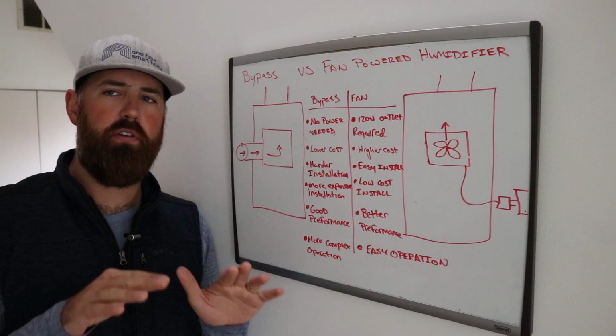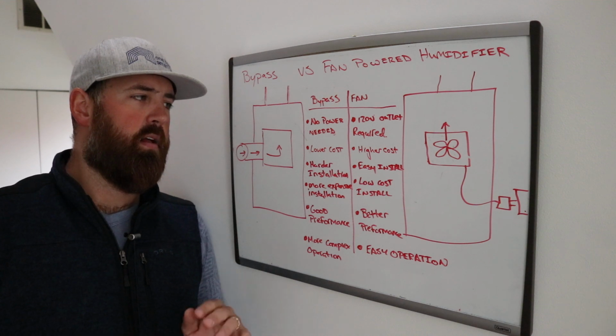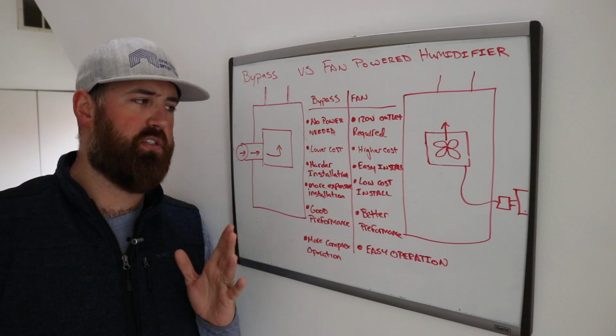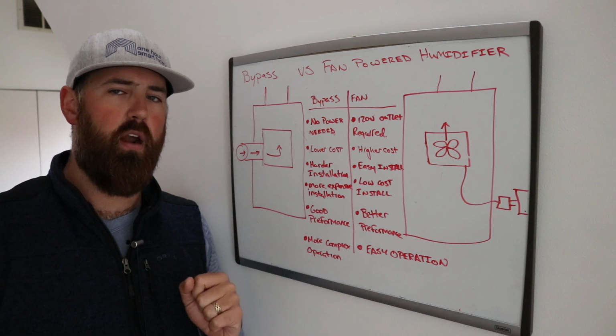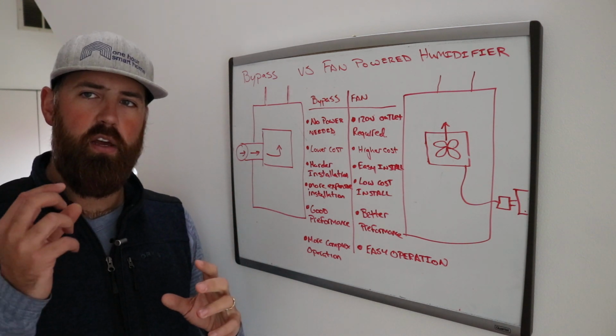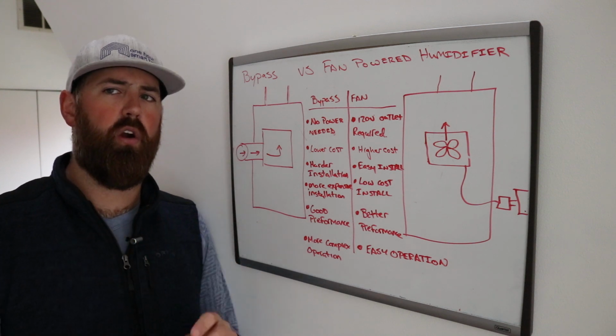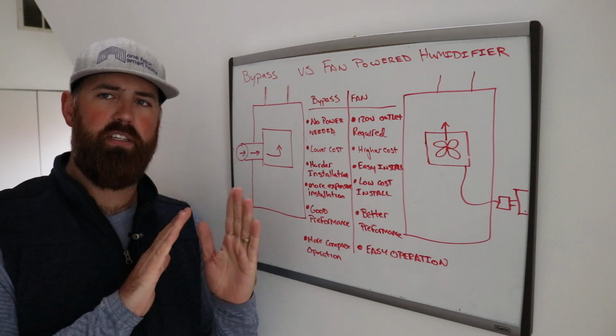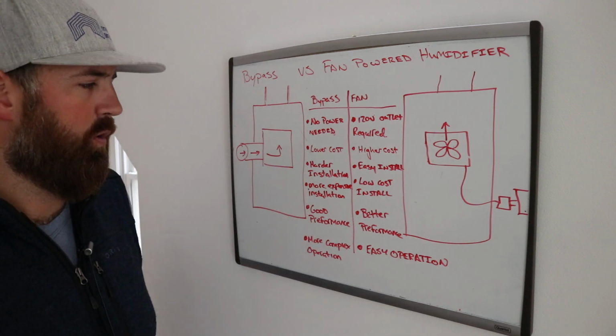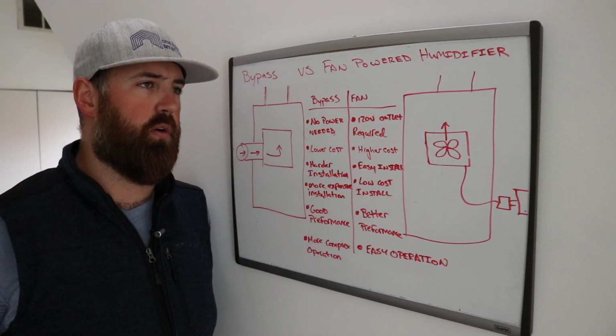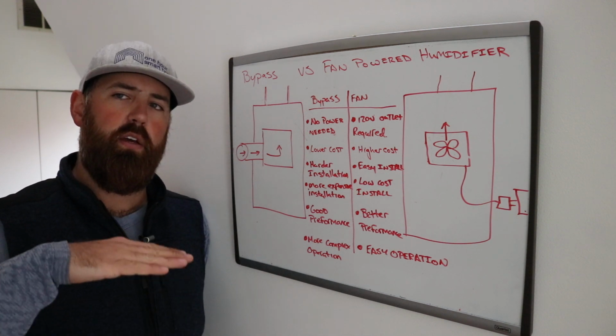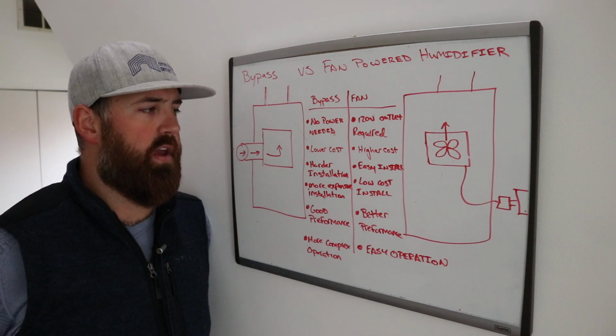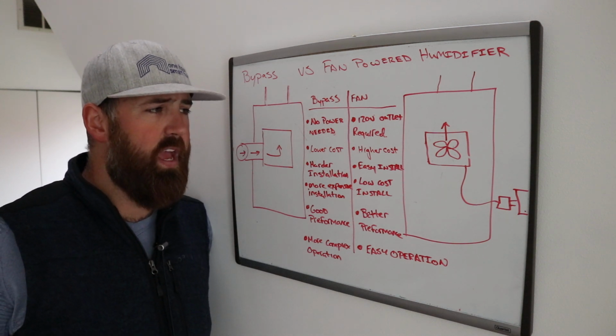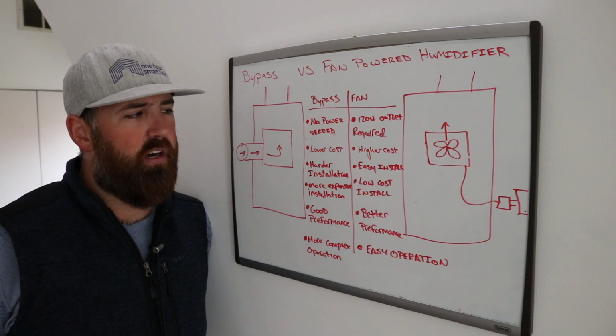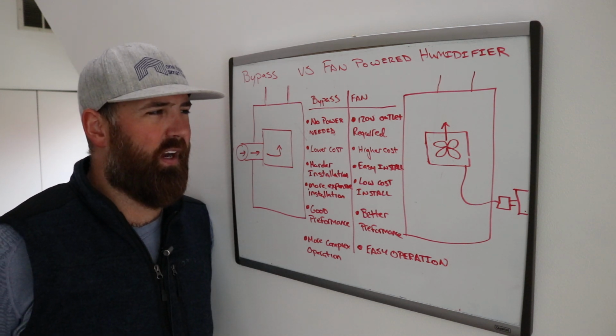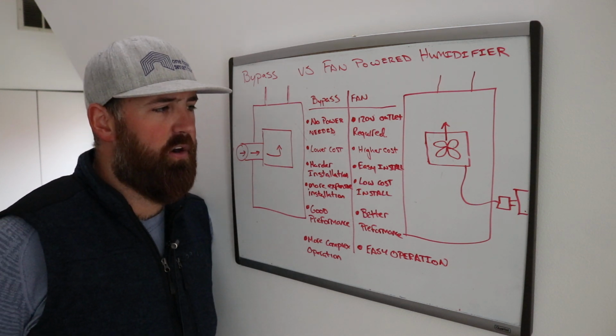However, when you go to install these things, it kind of evens out, because it is harder to install a bypass humidifier than it is a fan humidifier if you don't already have that additional ductwork, because you've got to cut the hole for the additional ductwork, route the ductwork, and sometimes with HVAC systems, there's not a lot of space to get back there. So this can be a more difficult installation, which raises that cost up. So while its initial product cost is low, it might be more expensive for the installation on a bypass humidifier. The fan-powered humidifiers do typically have a little bit higher cost. Sometimes you're looking somewhere in the $250 to $300 range.